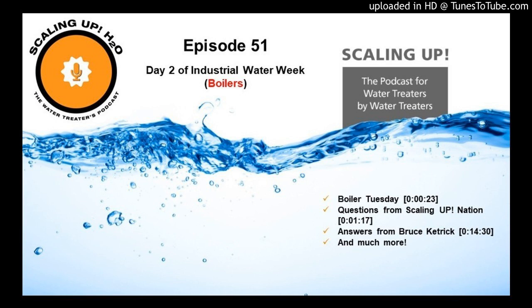So if we're getting water to carry over with the steam, we're not getting that 1,150-plus BTU powerhouse. We're now diluting it with 180 BTU water. So it's imperative for whatever that steam is going towards that we have nice, clean steam with the absence of water in it.